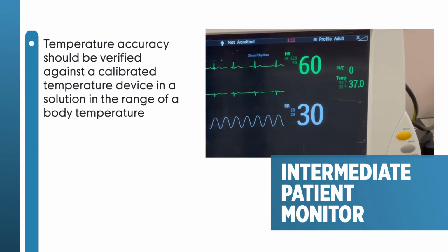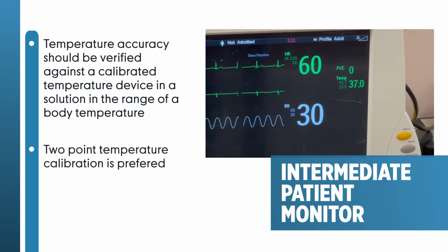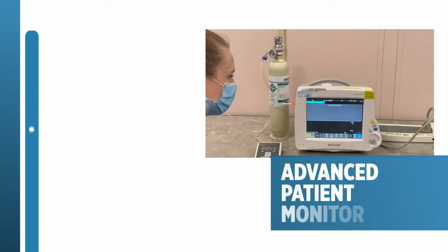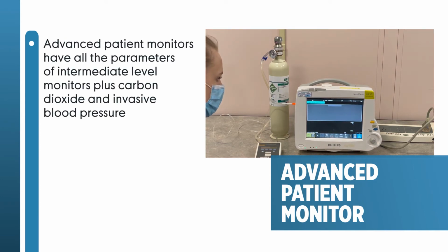Temperature accuracy should be verified against a calibrated temperature device in a solution which is in the range of body temperature. 2-point temperature calibration is preferred. Advanced patient monitors have all the parameters of intermediate level monitors, plus carbon dioxide and invasive blood pressure.